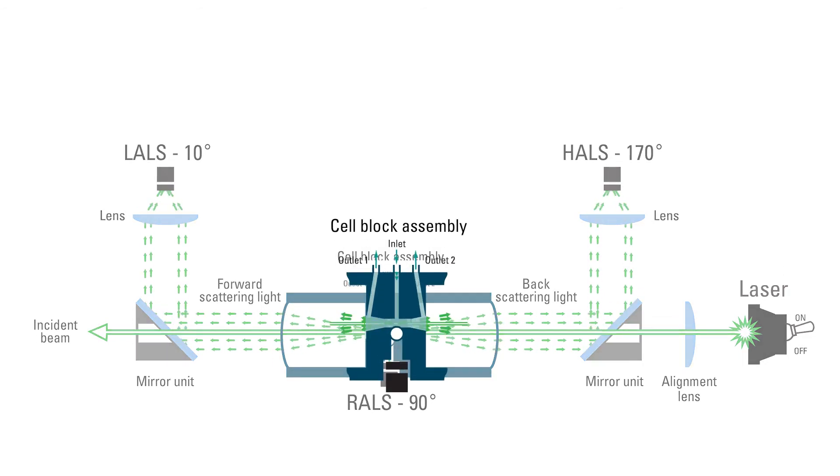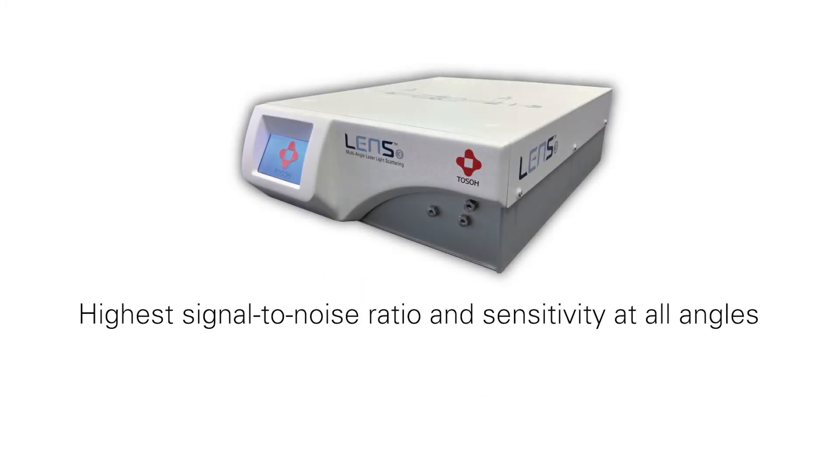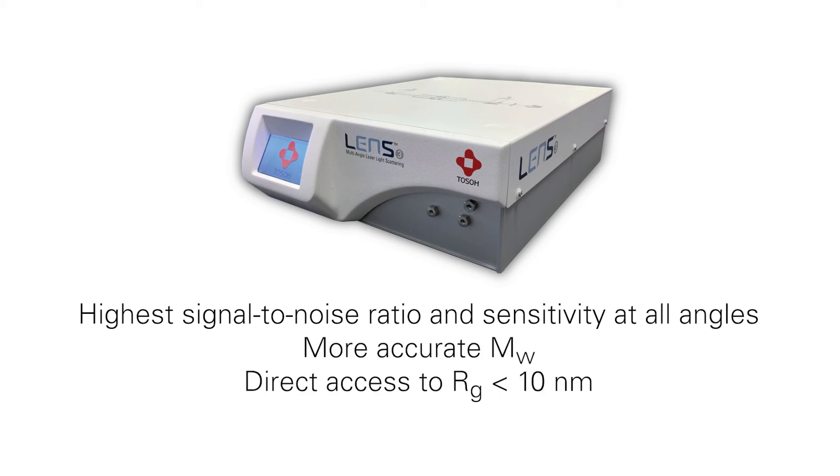The dual conical shape of the non-refractive material of the flow chamber eliminates undesired scattered light and reflection noise from stray light. This unique design offers the highest signal-to-noise ratio and sensitivity at all angles, resulting in more accurate molecular weight and direct access to the radius of gyration of molecules under 10 nanometers — for the first time by MALS.